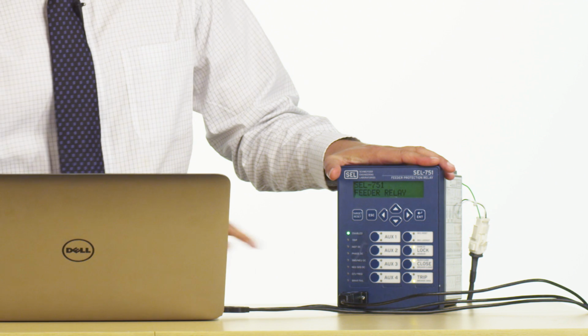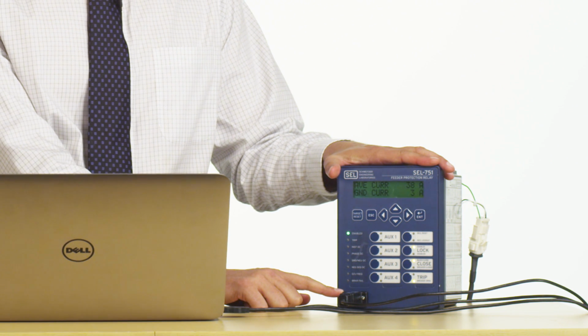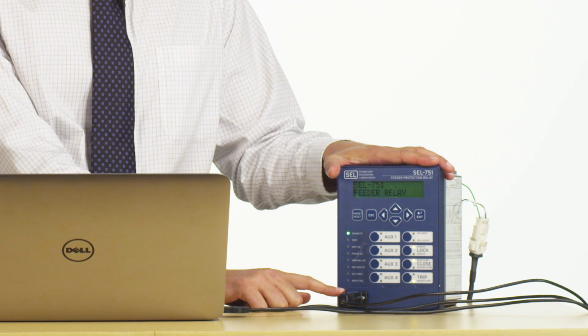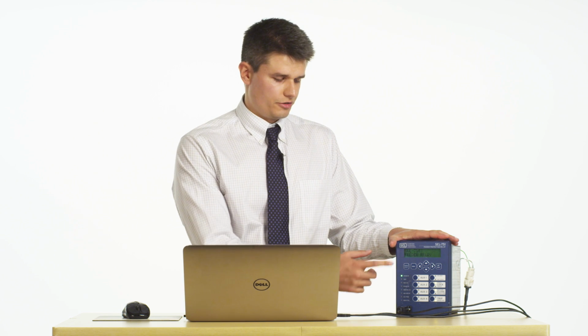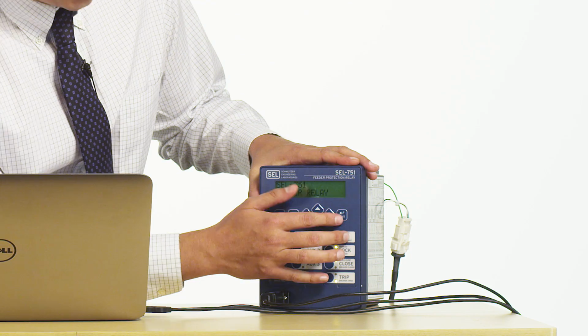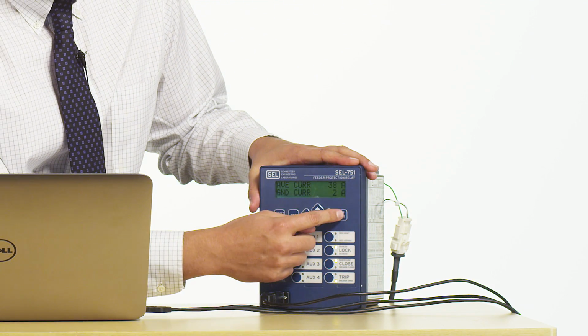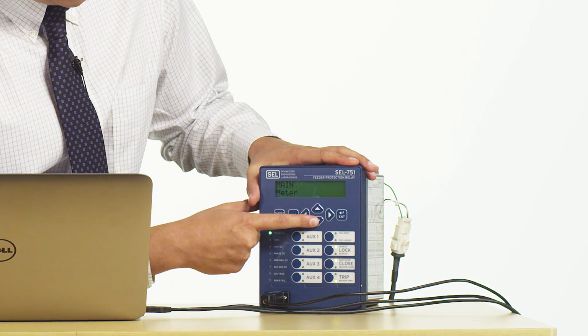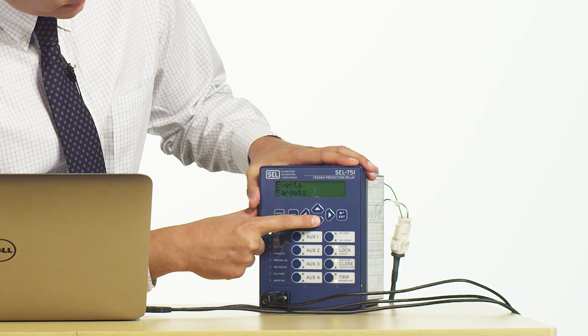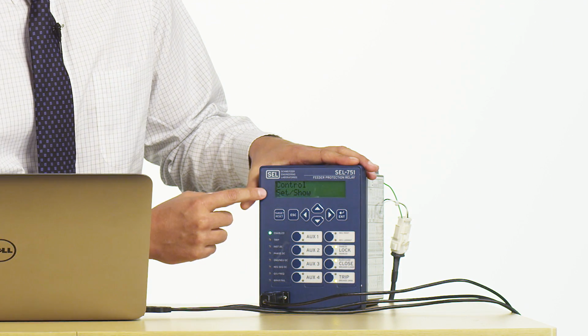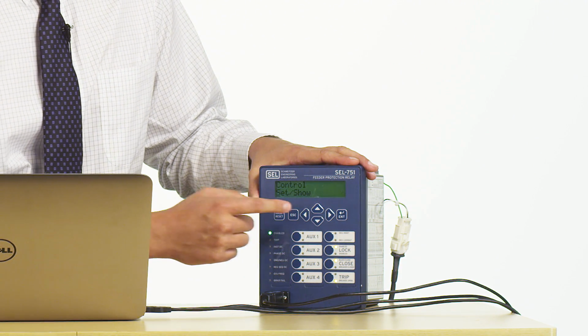You need to know what the front port communication speed is on the relay. That is a setting that we need to find out through the front port. The way you do that is you go into the main menu by hitting the enter button, and then you navigate down to the set show section and hit enter again.